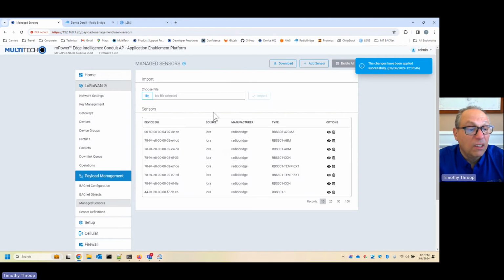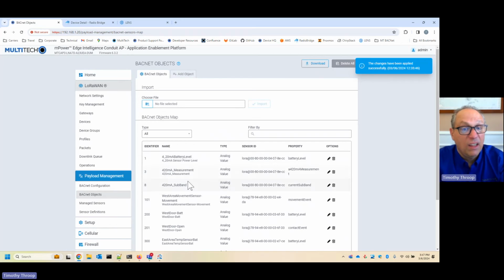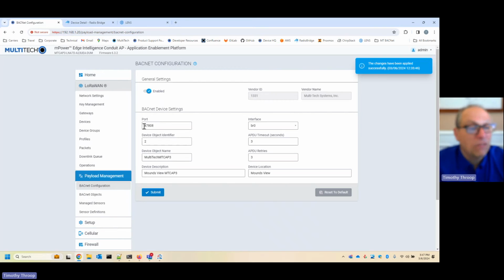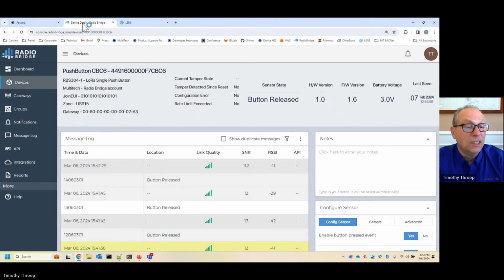The objects I've created are going to flow out on port 47808 by default and broadcast to the Tridium Niagara network, specifically the Jace controller. Now that I've got it showing up in Lens, in the conduit, and in Radio Bridge, I'm going to add it to the BACnet system.